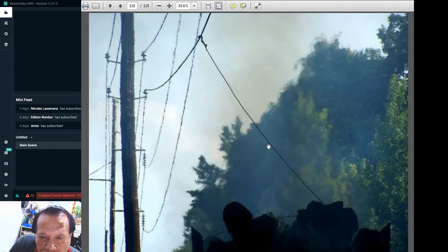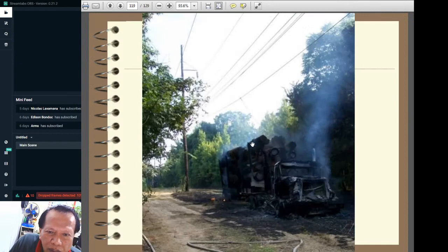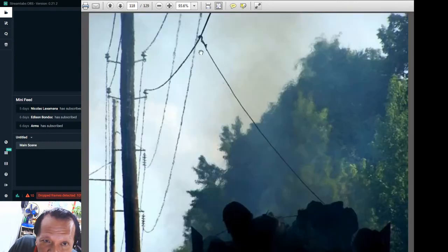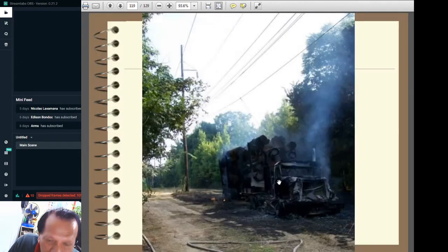And this one is showing a cable line which the driver of this truck threw a hook over and touched the high tension line. So you must be very careful. We have to see what is around us before we do something like this. What happened is that when the driver threw this hook, supposedly to tie the cable, the lugs, it got a short circuit, and of course his truck got burned.